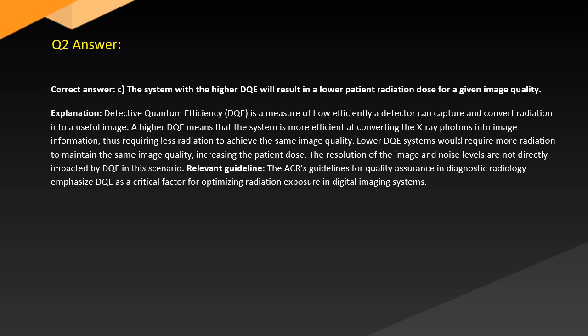Lower DQE systems would require more radiation to maintain the same image quality, increasing the patient dose. The resolution of the image and noise levels are not directly impacted by DQE in this scenario. Relevant guideline. The ACR's guidelines for quality assurance in diagnostic radiology emphasize DQE, a critical factor for optimizing radiation exposure in digital imaging systems.